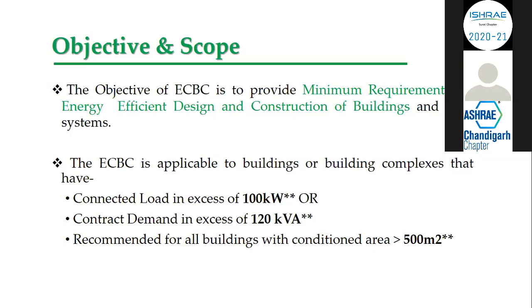ECBC is applicable to buildings with connected load more than 100 kilowatts, contract demand more than 120 kVA, and is recommended for all buildings having conditioned area more than 500 square meters. But there is a star mark over all three conditions.